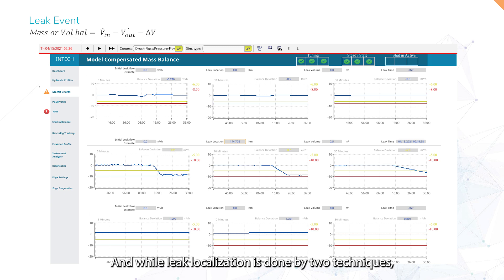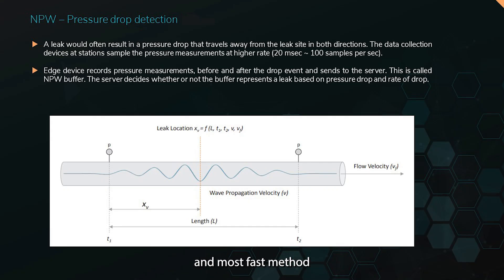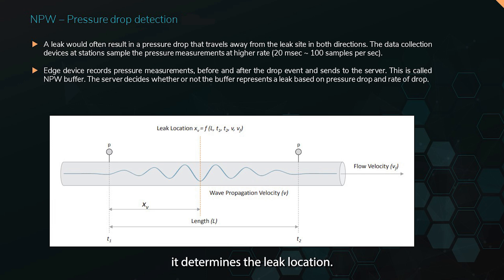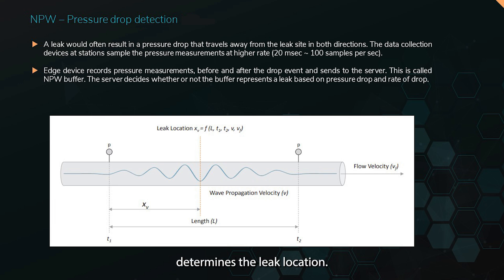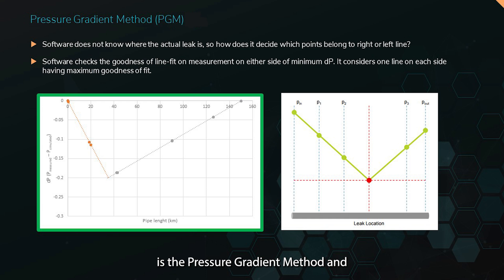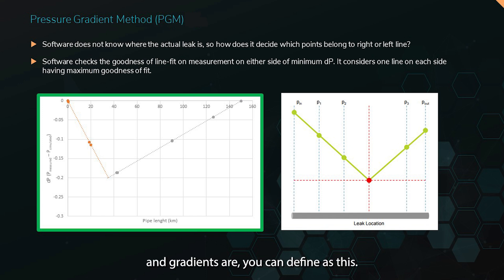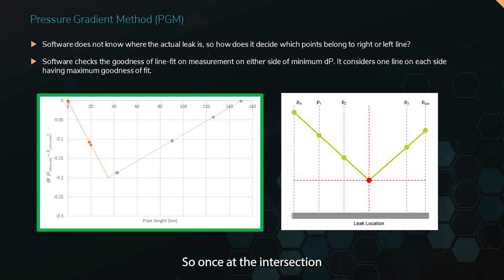Leak localization is done by two techniques: the negative pressure wave method, or NPW, and the pressure gradient method, or PGM. The NPW method is generally more reliable and faster for localizing a leak because it accounts for the speed of sound in the product and uses the time-of-flight method to determine leak location. It takes high-sampling-rate data from pressure instruments and sends it to the LDS server, which runs further calculations to precisely determine the leak location. The pressure gradient method complements NPW by plotting gradients on both sides of the leak — defined as the difference between pressure measurements under leak and no-leak conditions — and the software calculates the leak location at the intersection of those gradients.